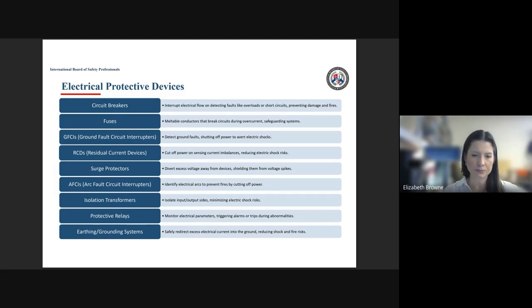voltage spikes. There's also arc fault circuit interrupters that can be utilized in those big motor control centers that we talked about, that will identify electrical arc potential and prevent fires by cutting off the power. There's also isolation transformers that isolate input and output sides that minimize electric shock risk. There are protective relays. Those monitor parameters of electrical current and voltage, and it would trigger an alarm or a trip to the equipment if it detects any abnormality.